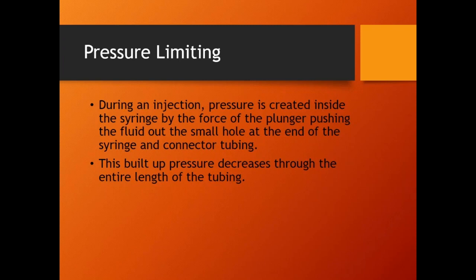Now, about the other thing I said, I don't know why they would pick 325 or something. IV needles are rated at 400-plus psi. These only go up to 300. I get the question because they have the ability to select 200 psi, 100 psi. To this day, I've been teaching this for 13, 14 years, and I have no idea why operators would not pick anything less than 300 psi. Because that can cause a problem. I'll talk about that in a second.